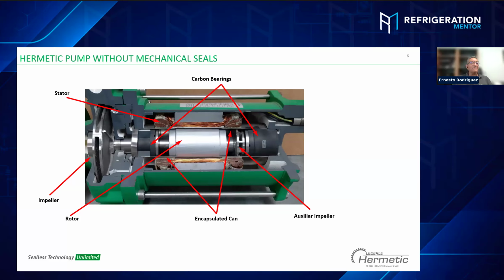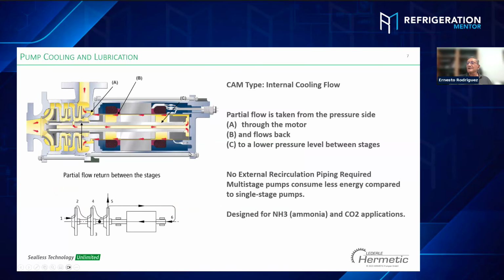I want to explain what the problems or the causes of the flash gas for CO2 are. This is a critical situation for CO2 versus the oil-based refrigerants. Definitely stick around. We'll get into that on the flash gas and how to prevent that stuff. So, yeah, exactly. It's correct.